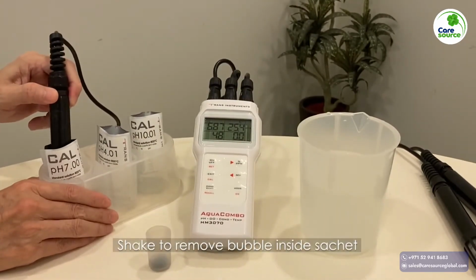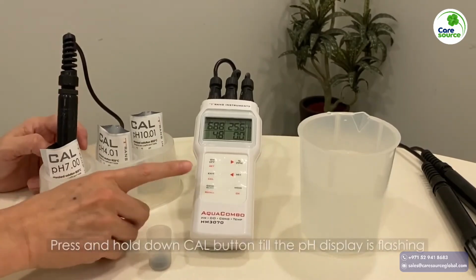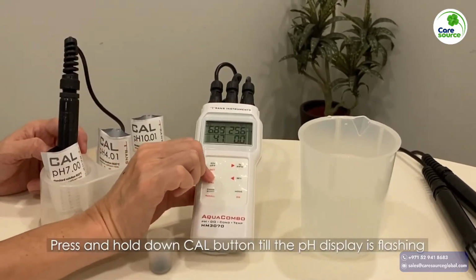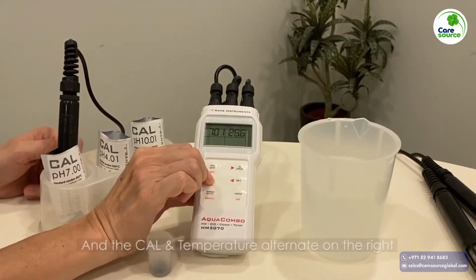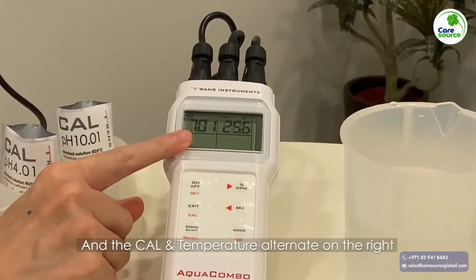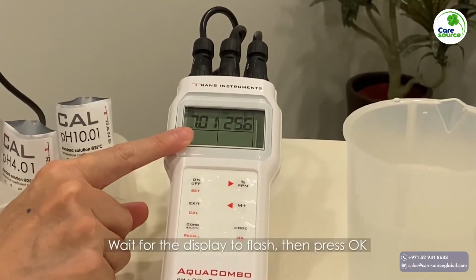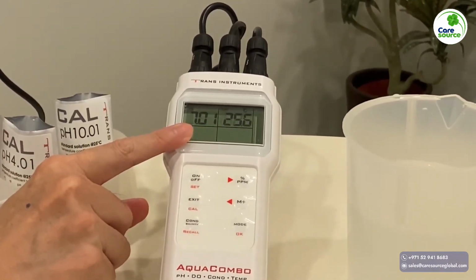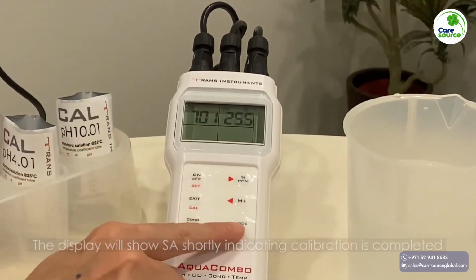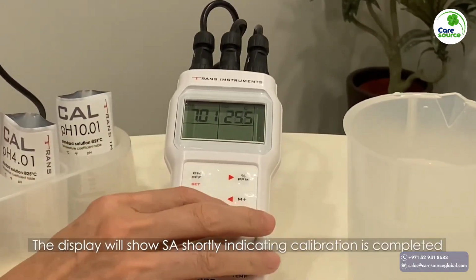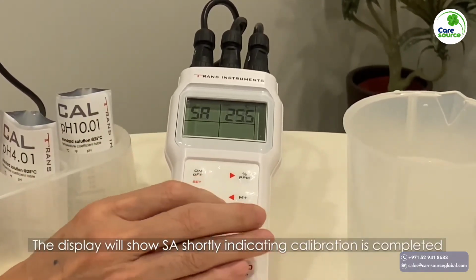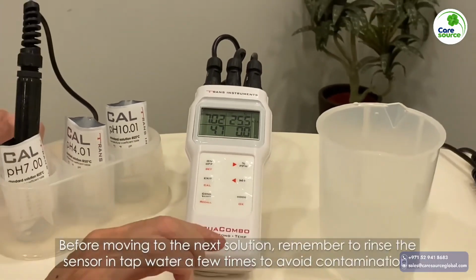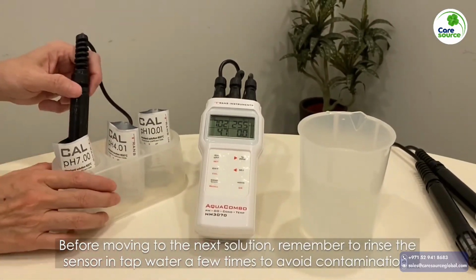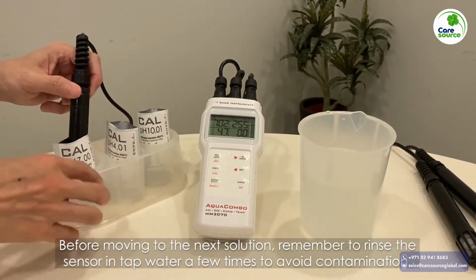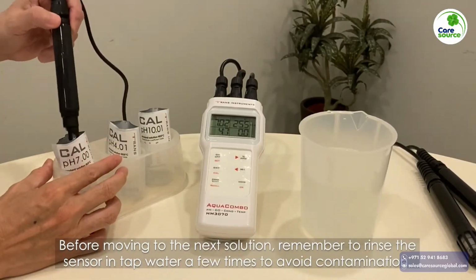Shake to remove bubbles inside the sachet. Press and hold down the Cal button until the pH display is flashing, and the Cal and temperature alternate on the right. Wait for the display to flash, then press OK. The display will show SA shortly, indicating calibration is completed. Before moving to the next solution, remember to rinse the sensor in tap water a few times to avoid contamination.